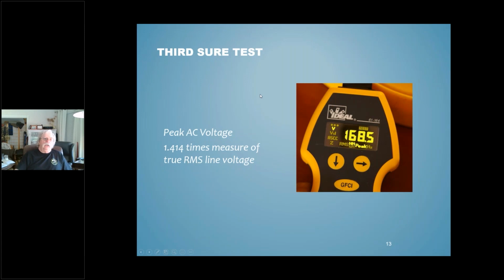AC peak voltage is kind of interesting. If you had an oscilloscope, this would be the voltage reading at the very top or bottom of the sine wave peak. And this has some value to us from a diagnostic point of view. It can help us to determine if there's an extreme amount of harmonic distortion in the power feed. You have to compare your measured reading here to what the line voltage was. I think, as I recall, we had 119. We multiply that times 1.414 to determine what we should get.